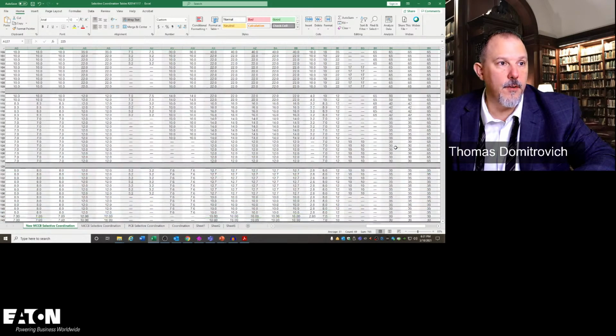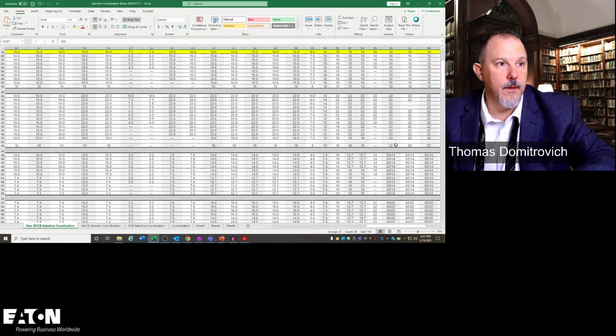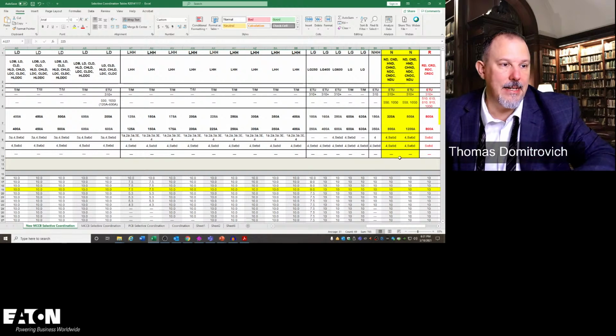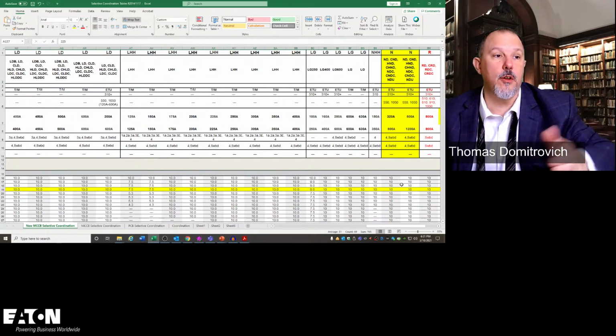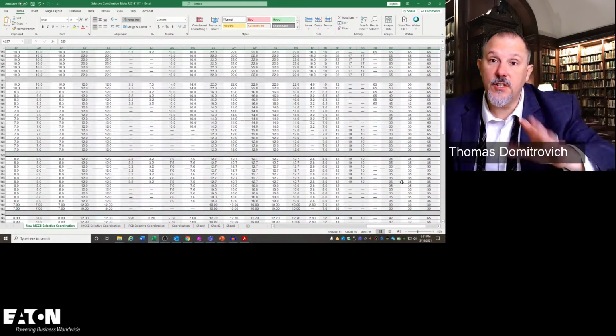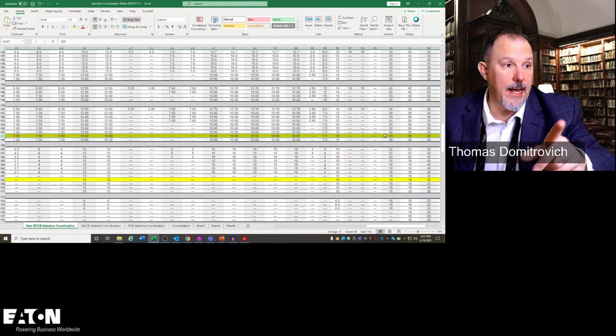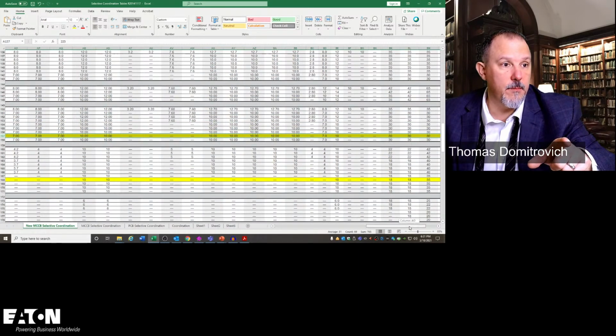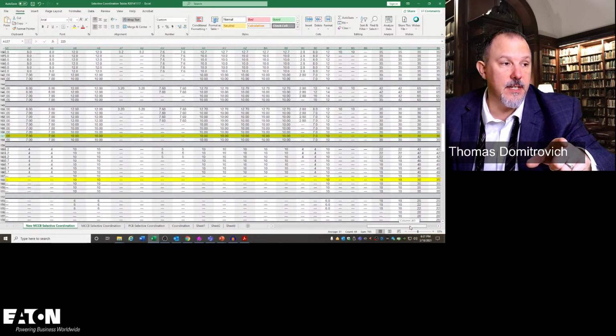Ooh, I can go to 30. Where am I at? Again, an ND, so that wouldn't have gotten me too much. Even if I used the fuse downstream, I would not be into a smaller breaker upstream. So these are the things you need to do. You need to look at the coordination between these breakers, and this is how you use the tables.